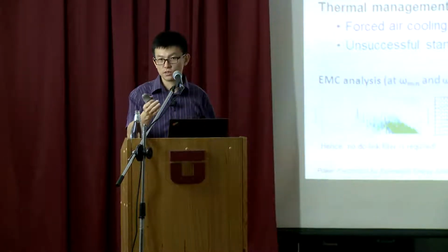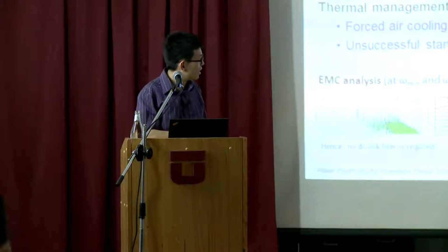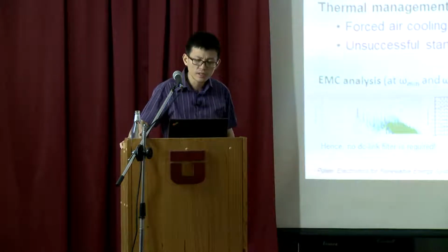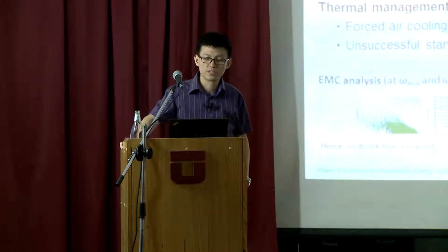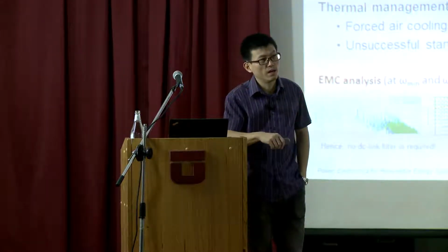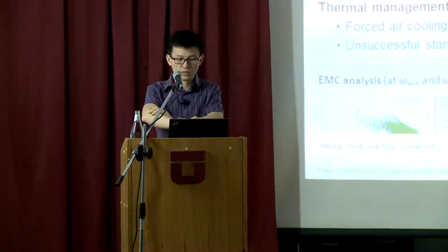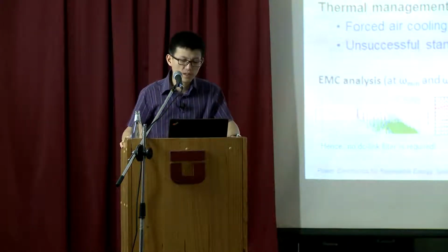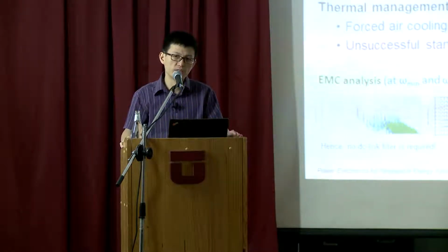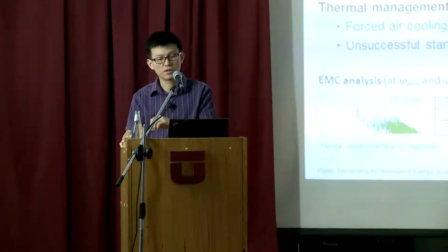I don't know if you guys do power electronics design. I think most of you probably do the power electronics, the converter design. One of the key things you really have to consider is thermal management. It is very important. For silicon devices, you always choose a device and then do thermal management, so thermal simulation. Normally we use PLECS. I don't know if yesterday Gianpaolo guided you through this PLECS software. Normally you can input the characteristics of the devices, and then you calculate losses at different operating points. And then based on these thermal losses, you can design your thermal management system.